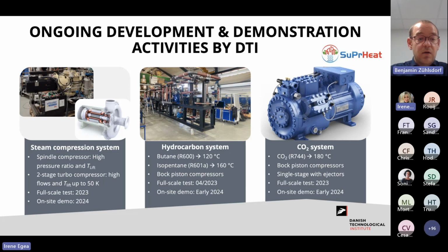So we can see here, for example, the steam compressors we're working on. That's a combined system of turbo compressors, 2 turbo compressors directly driven, and a spindle compressor. Turbo compressors in a 2-stage arrangement can lift around 50 Kelvin. The spindle compressor has a higher temperature lift, and actually the spindle compressor is right now down here in our laboratory, and we are testing it for, let's say, proof of concept, and then we'll upscale to higher capacities. We go for full-scale testing by the end of '23, and hope for on-site demonstrations in '24.